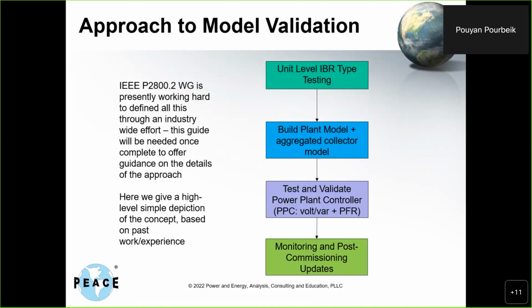Then you test and validate that the plant controller and the overall plant responds the way the model responds, as you'd see in the field, for things like volt-var and primary frequency response, etc. That piece you test in the field at the actual plant. Following that into the future, you can monitor and do post-commissioning updates - if a grid event happens, you take that and play it back into the model to see if it still behaves adequately. That gives you a complete picture.